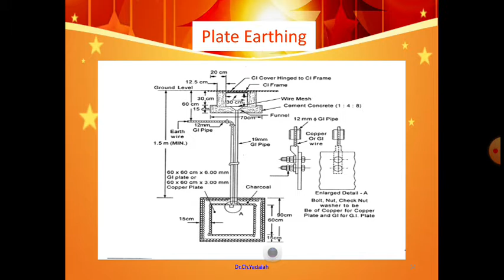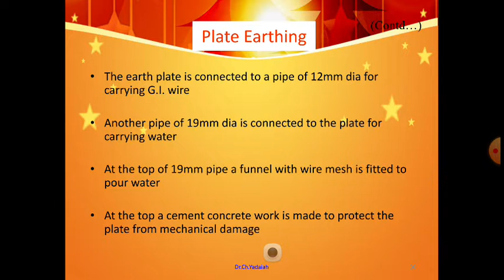Now, knowing this, let us do the schedule once again. So similarly, we are going to do the schedule. What is the schedule we are going to do here? We are going to use a 60 centimeters into 60 centimeters, 6 mm GI or 3 mm copper plate. 19 mm dia GI pipe, 1 number is required, and 12 mm dia GI pipe, 3 meters is required. GI wire SWG 8, 5 meters is required, and 30 into 30 centimeters cast iron frame, 1 number required, and GI lugs and nuts and bolts, lock nuts, washers, 5 sets is required.